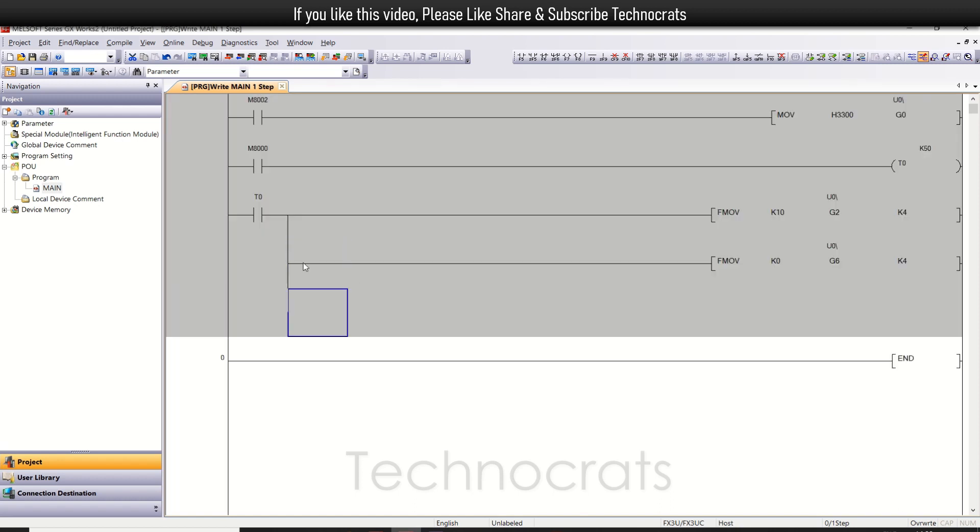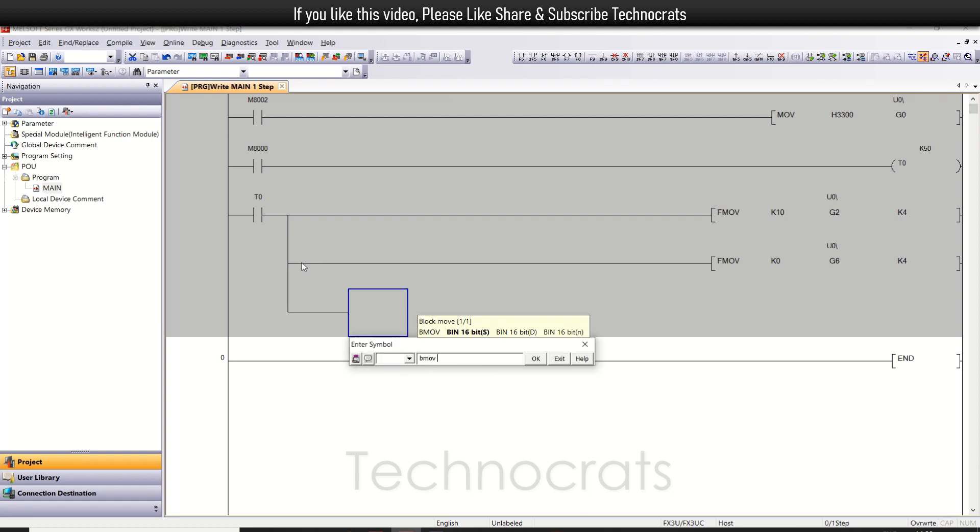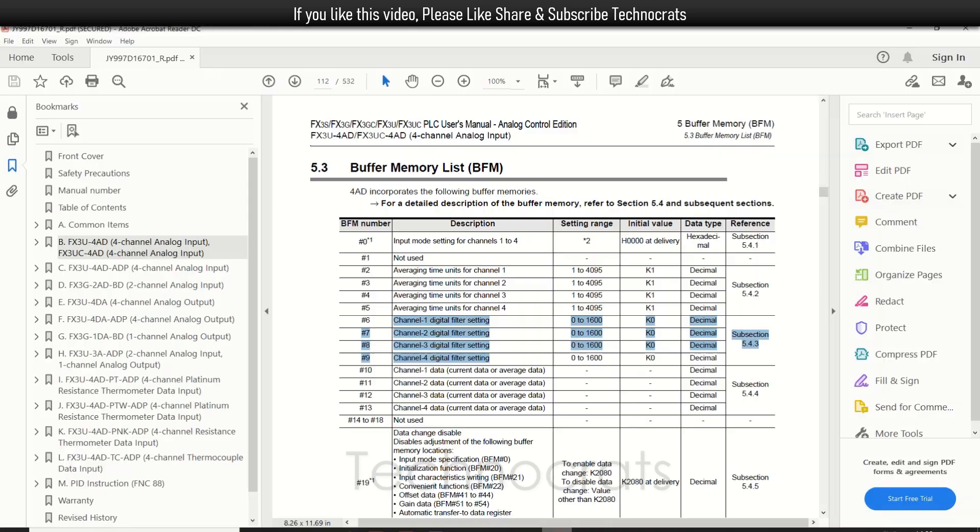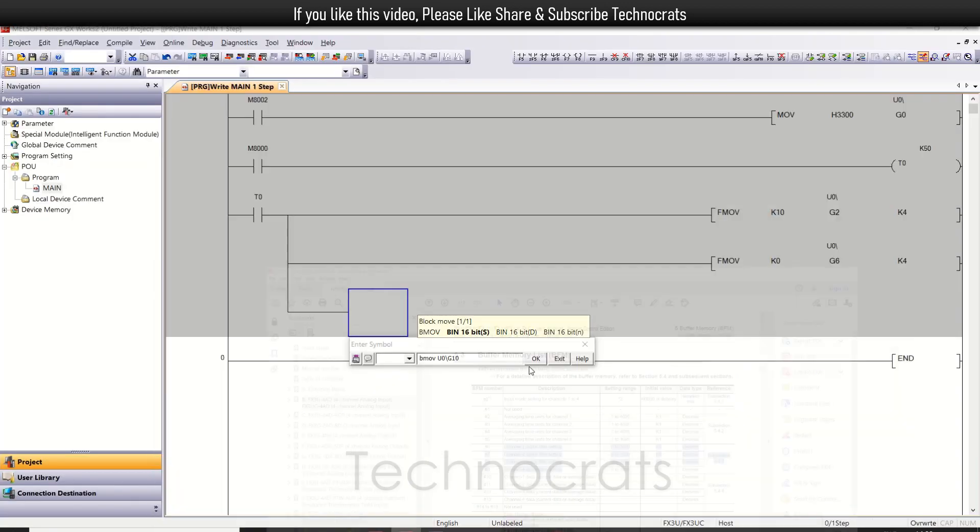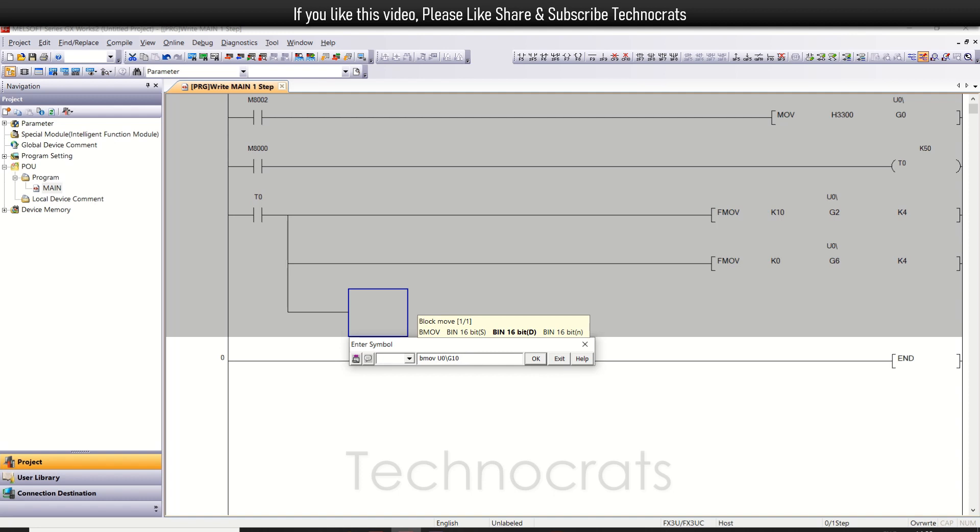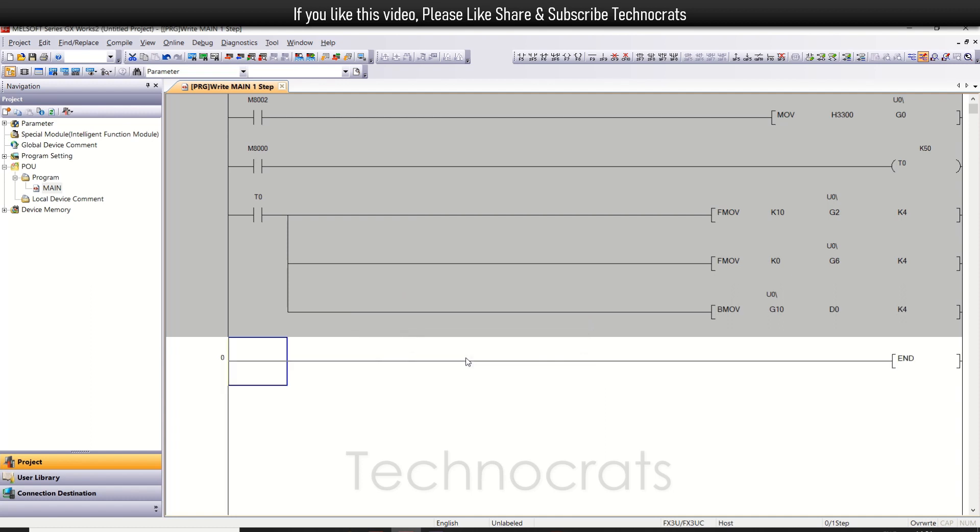Now let us read the value. I will use BMOVE. I want to move the value of G10, 11, 12, and 13 to data registers. So I will use BMOVE from U0\G10 to D0. The value corresponding to U0\G10 will move to D0, then G11 will move to D1, G12 will move to D2, and G13 will move to D3. So that is K4 values. This is all you have to do for the programming to read the input value.